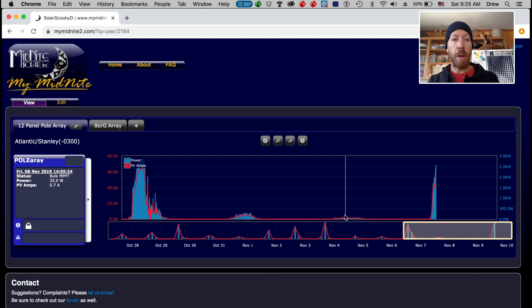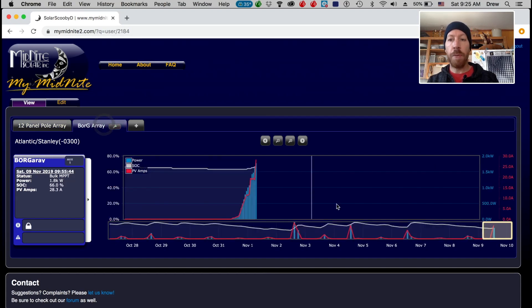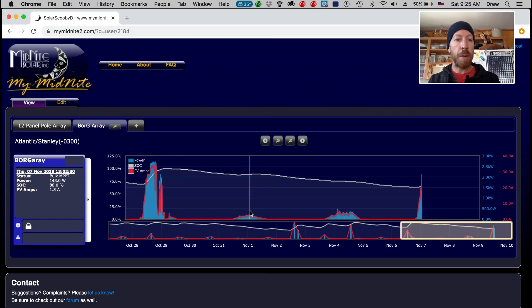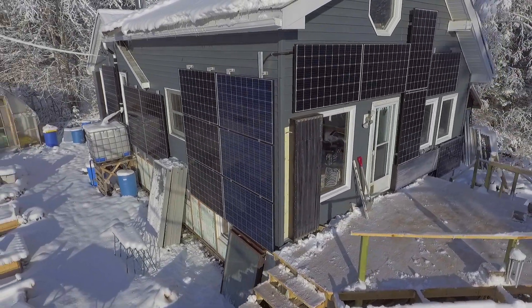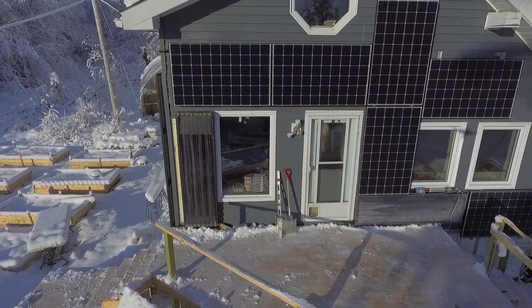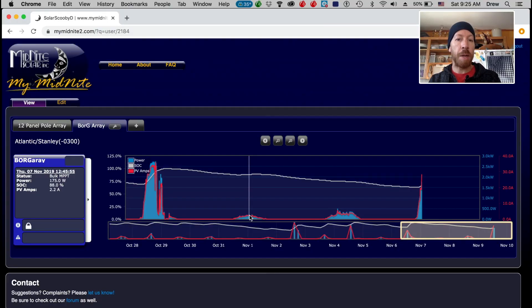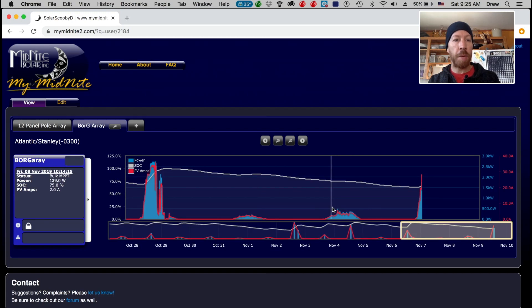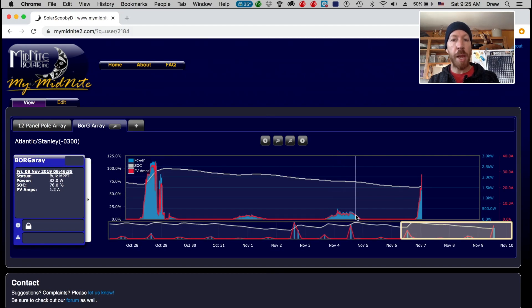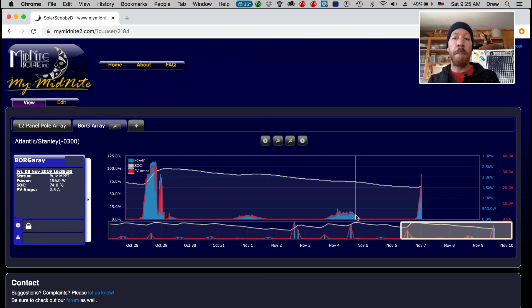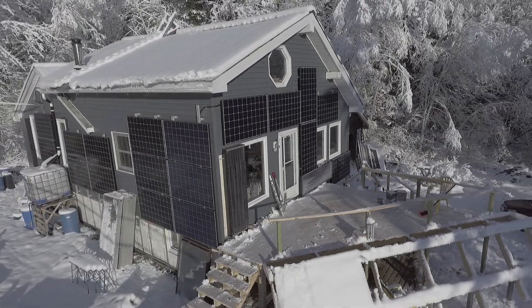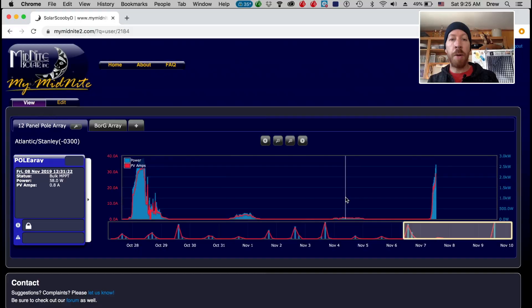If we look at the house array, we get a different kind of story. We had our full charge back here on November 6, and then on the house array, because it's covered with the overhangs from the roof and those panels never got covered, I'm continuously making 100 to 200 watts of power on the first day of the snowstorm. Then on the second day of the snowstorm I'm also making 300 or 400 watts all throughout the day. So we were able to actually produce about 3 or 4 kilowatts on this stormy day, even though it was really dark. Most of that came from the solar panels on the house which were perfectly clear, while the solar panels that were out on the pole were covered in snow and doing very little.